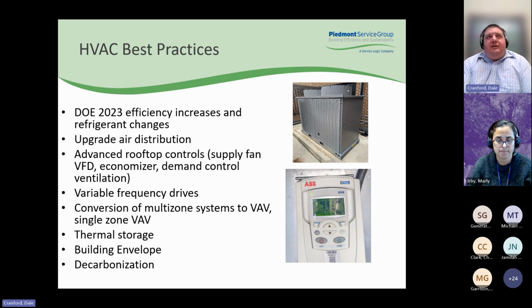Another best practice for HVAC is variable frequency drives. You can put those on fans and pumps, trying to help reduce energy using fan laws and taking advantage of the relationship between speed and power being a cube relationship. So there's significant energy savings there.